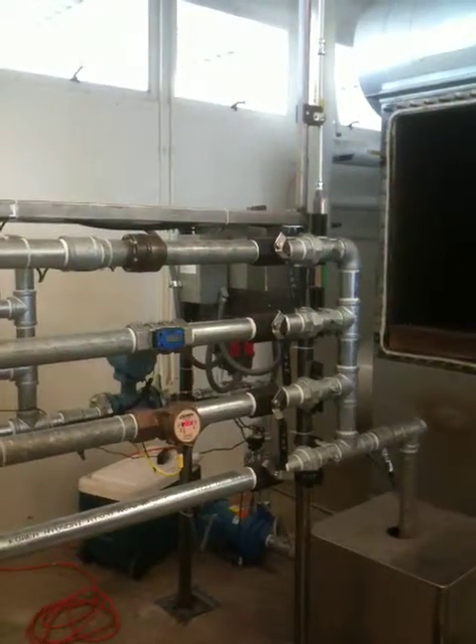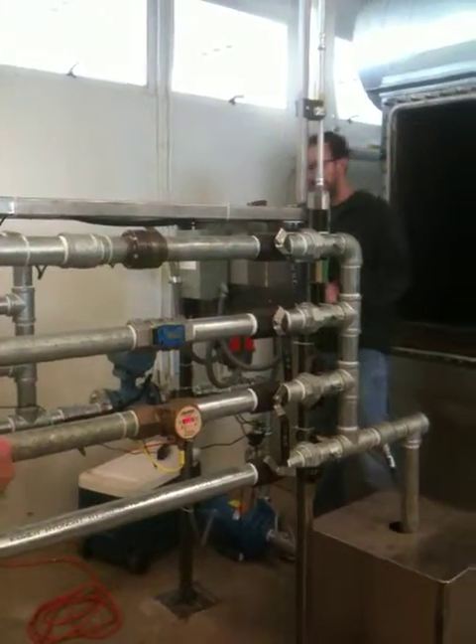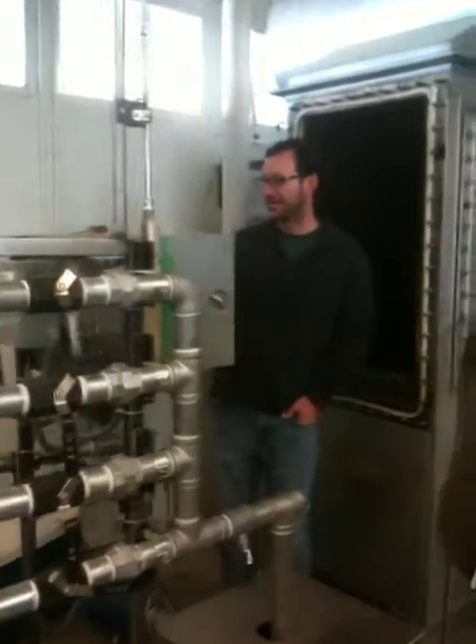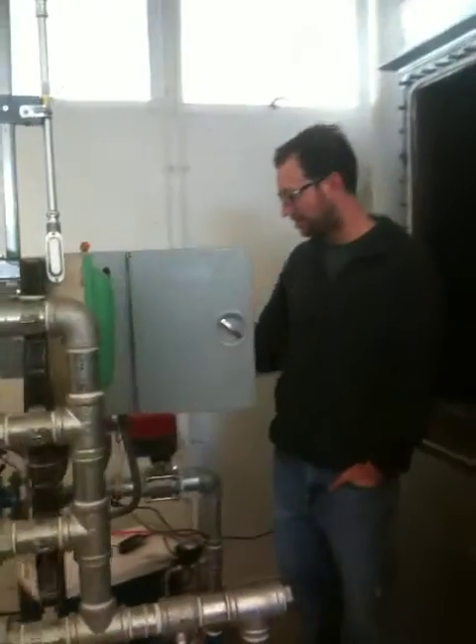So for the pump curve, you want to do 2 different speeds. So here's a variable frequency drive that changes the speed of the pump. So I'm going to put it at 45 hertz first, and then you can do 60 hertz, which will be the maximum. So you can see the valves are open, you can hear the water flowing through there. If you look at the screen, it probably tells you what the flow rate is, and the pressure difference across the pump. So I think the valve's pretty much fully open right now.